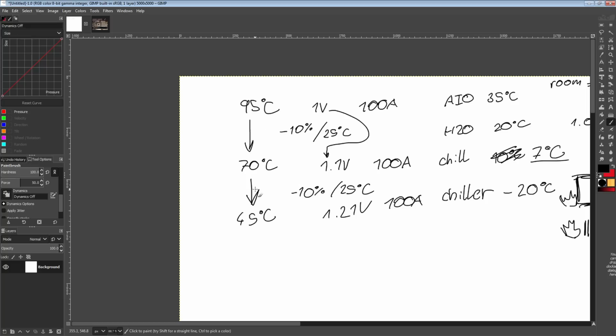A lot of people, as soon as their new cooling system runs 10 degrees cooler, their idea is to just crank up the voltage until they're back up at the thermal limit, right back up at 95 degrees. And then it's like, well, that's why you're getting degradation, because your current draw hasn't changed, your voltage is higher. You need to maintain the lower temperature.